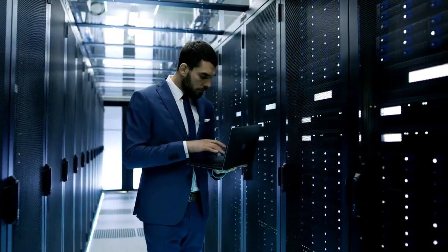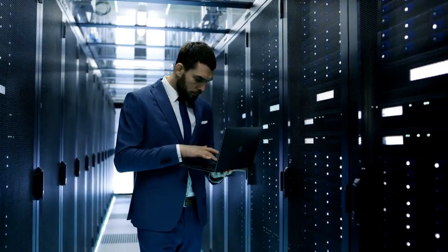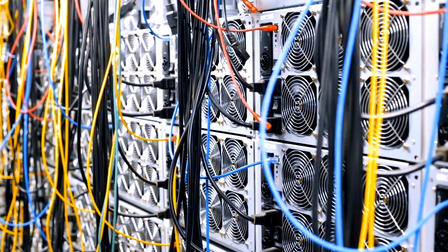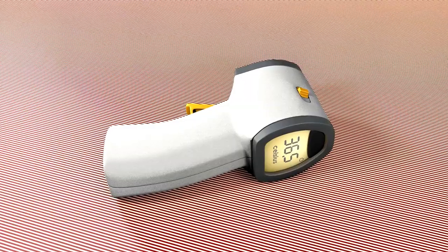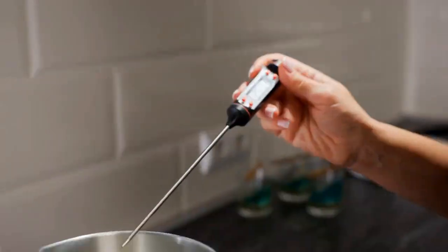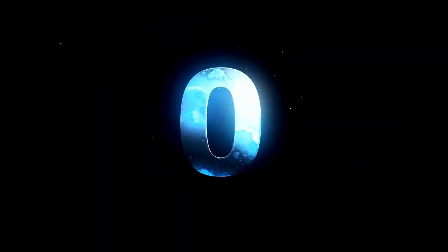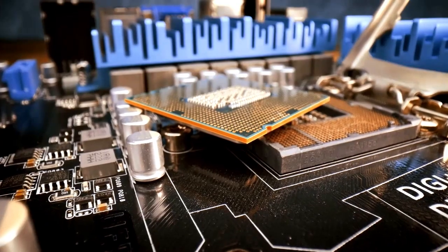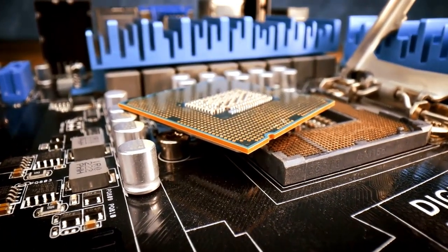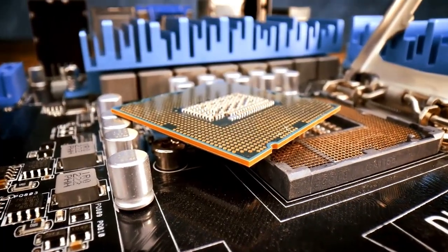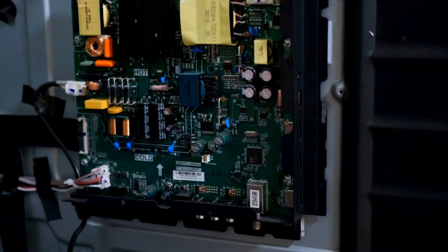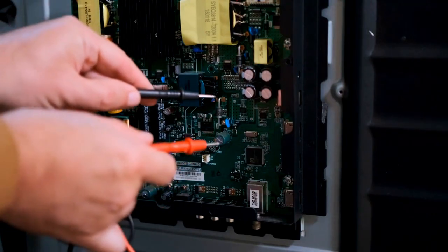If someone attempts to rely on air to cool a rack operating above this physical limit, the consequences are swift and catastrophic. Real-world evidence confirms that when high-density cooling fails, the ambient temperature of a server room can spike from a comfortable 72 degrees Fahrenheit to over 90 degrees Fahrenheit in exactly 75 seconds. If left unchecked, the silicon processors will undergo severe thermal throttling, desperately slowing their own performance to avoid melting, before eventually suffering permanent, irreversible hardware degradation.